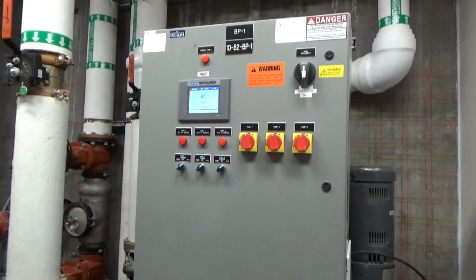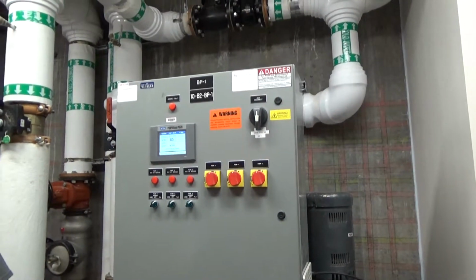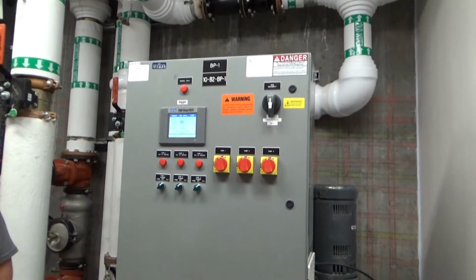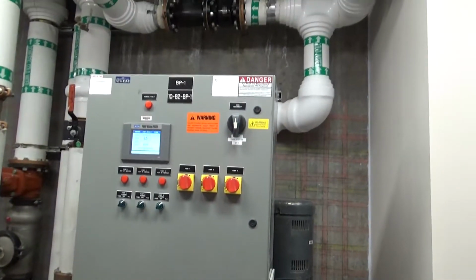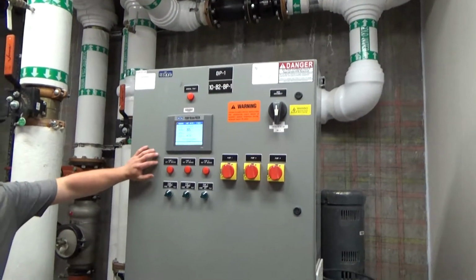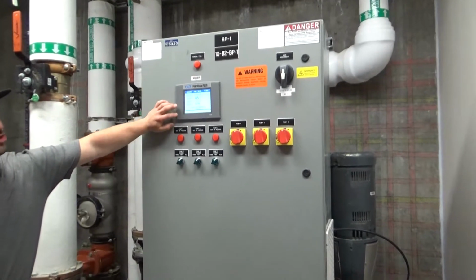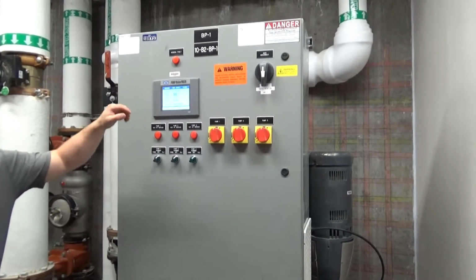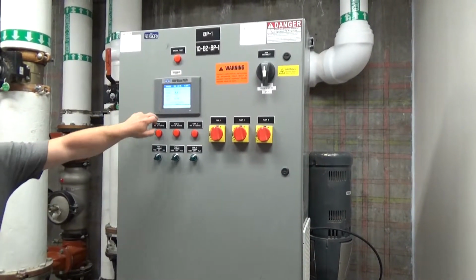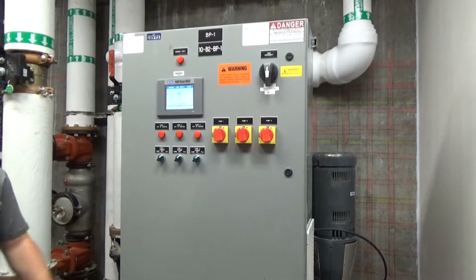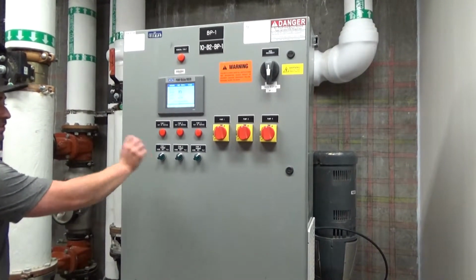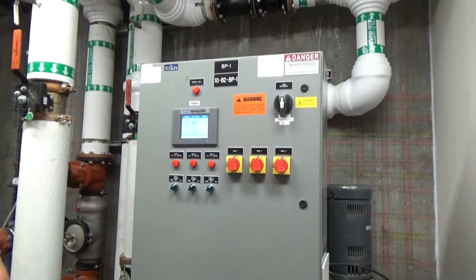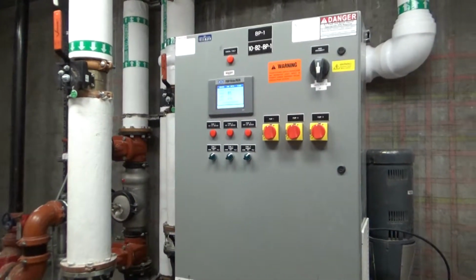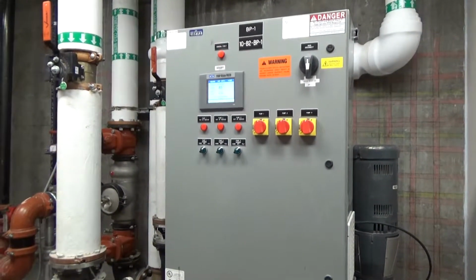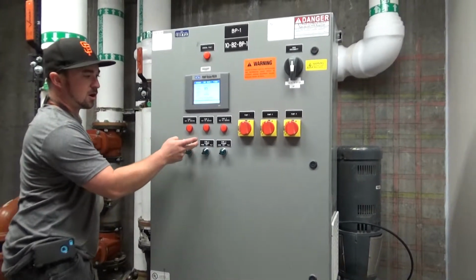So just for quick, the hand doesn't run 100%, it still runs? The hand runs it at a set speed. So when we come to do startup, we find out what percentage of the drive gets you a couple psi less than what you guys want. And so we input that on every single pump for the hand speed. So yeah, flicking into hand, it's going to get you about 82, 83, somewhere in that range. So, like I said, hand-off-auto for all 3.